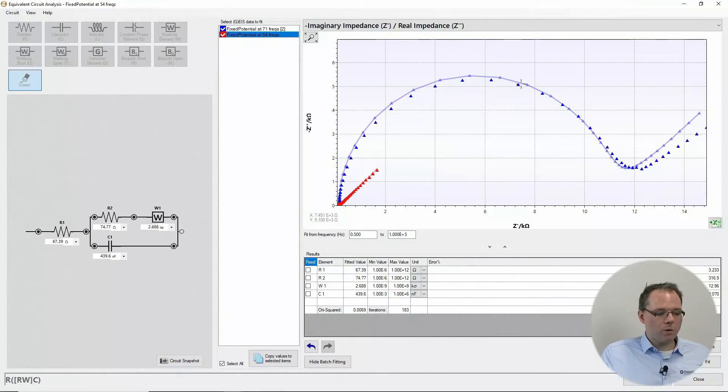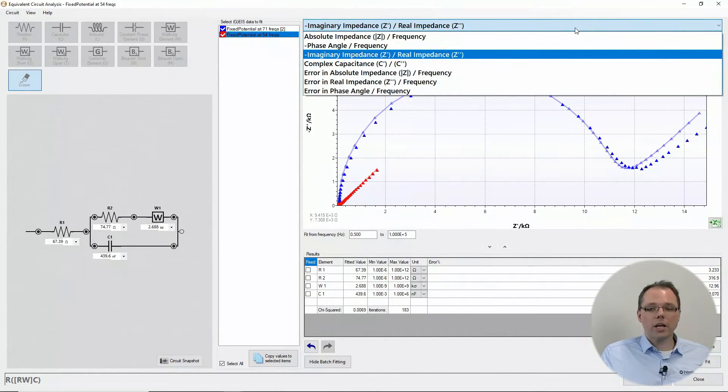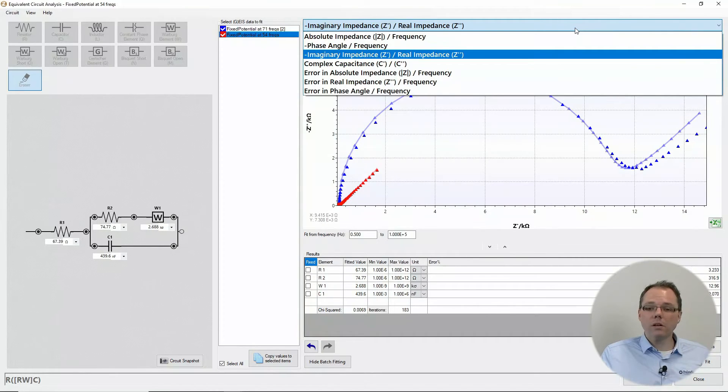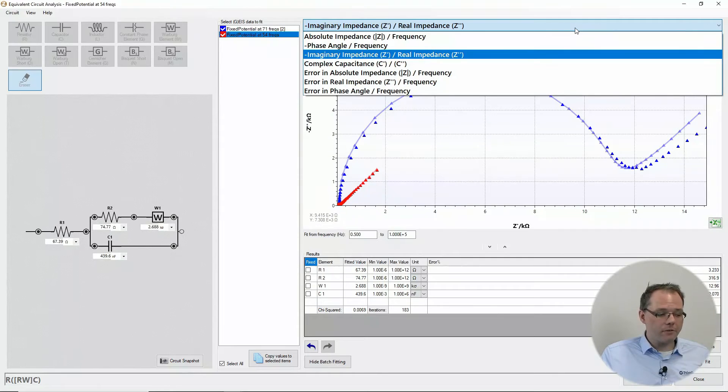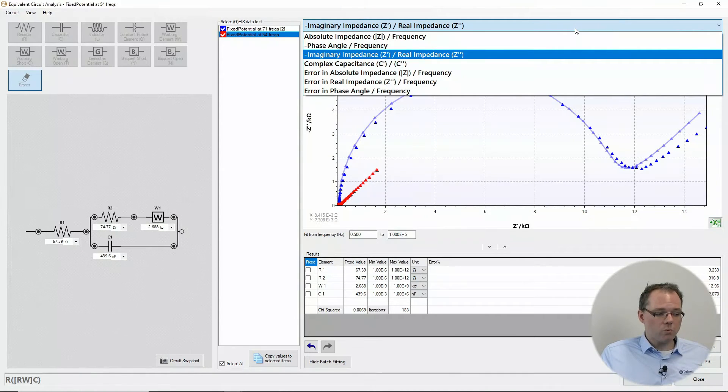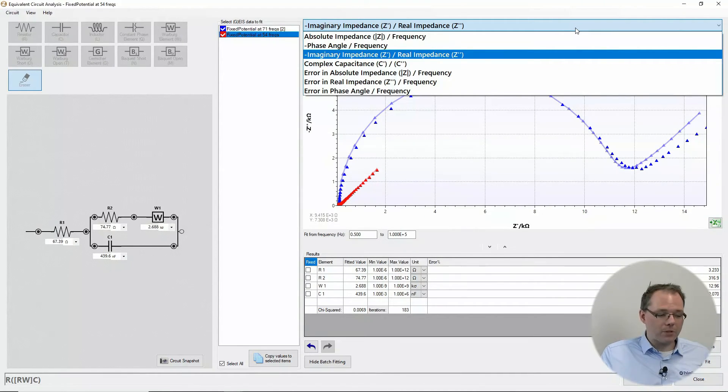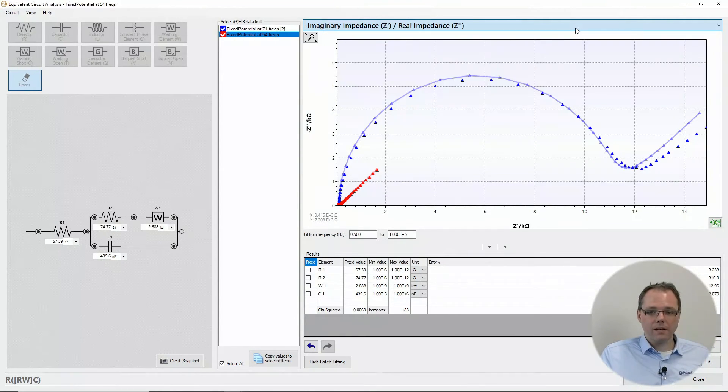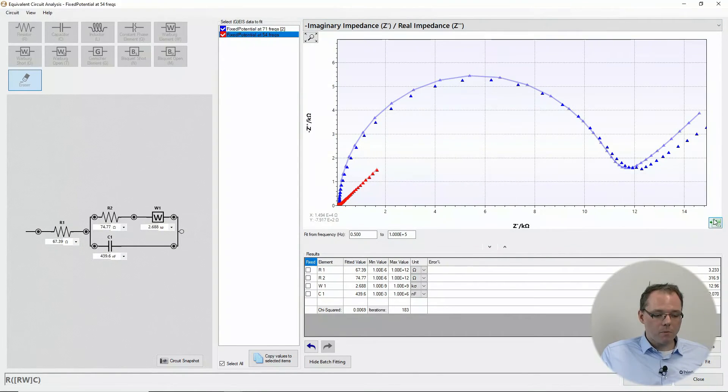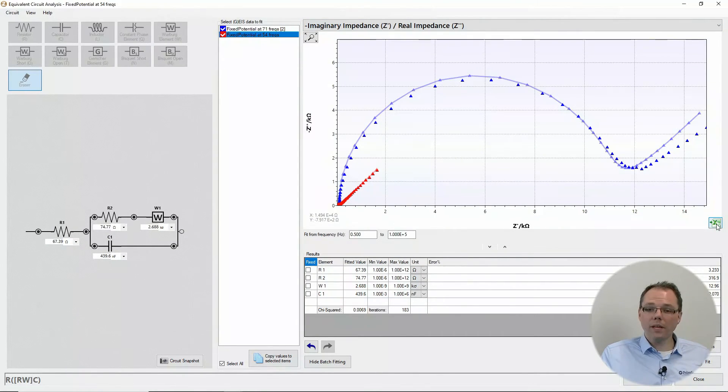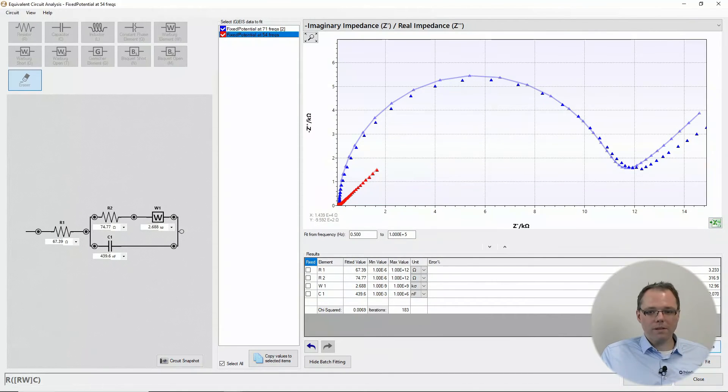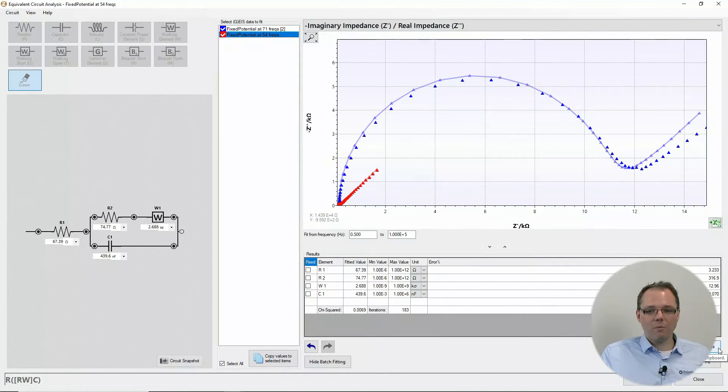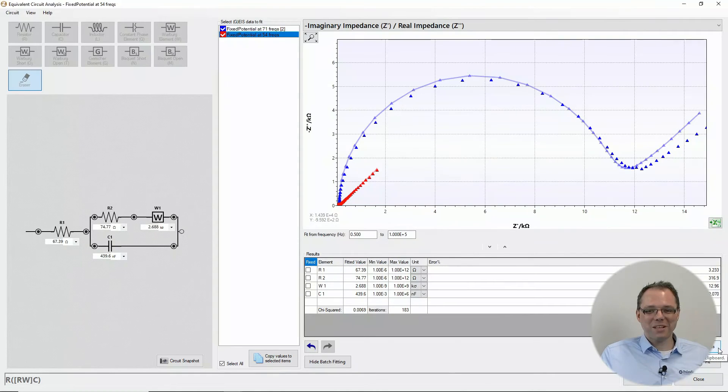One more or two more important things. Here you can change the plot that you actually want to look at. Usually it's the Nyquist plot, but maybe you just want to look at the phase angle or absolute impedance, which are the components of the Bode plot. With one click you can export the whole thing to Excel if you want to, and you can also copy the single results of a curve with the button that's hidden here beneath my portrait.